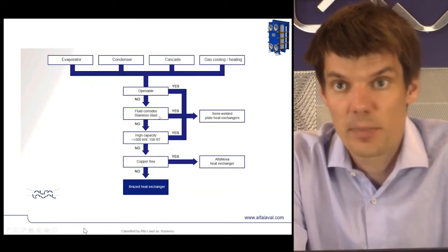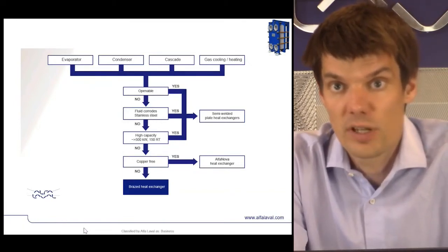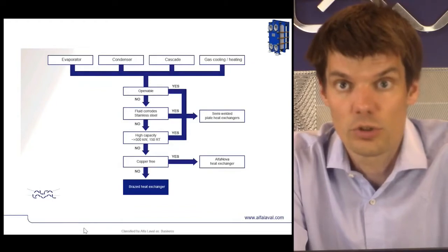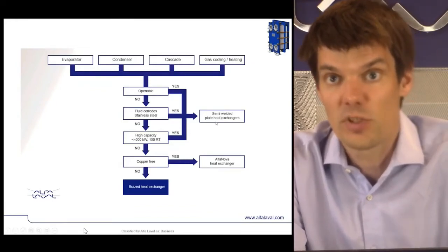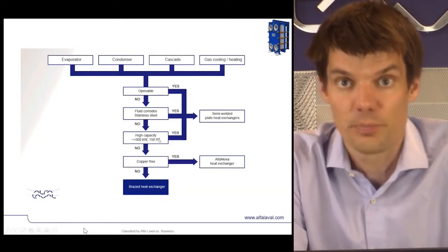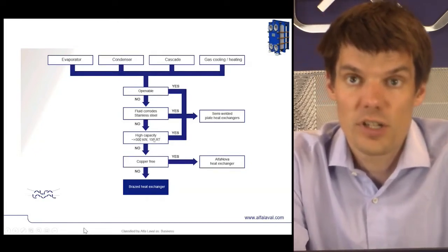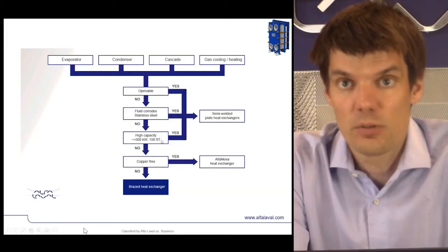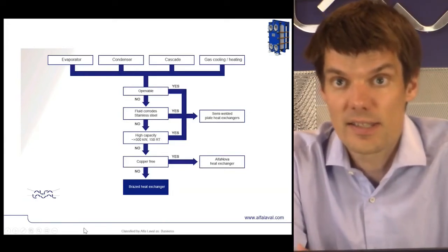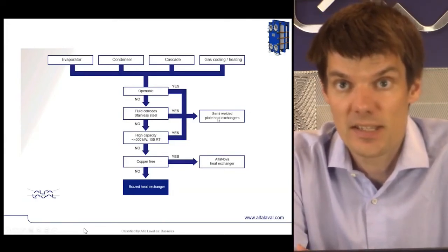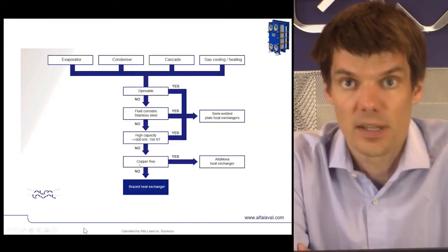The same goes for if the application uses a secondary fluid like calcium chloride or salt water, which corrodes stainless steel. Then the semi-welded plate heat exchanger with titanium plates is the best solution. Or if we are dealing with a high capacity duty, where the industrial size of the semi-welded plate heat exchanger makes it the preferred solution.